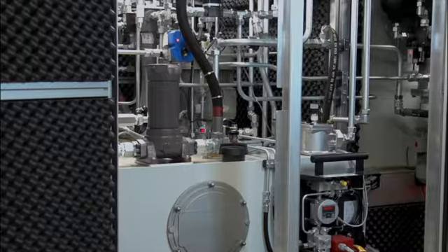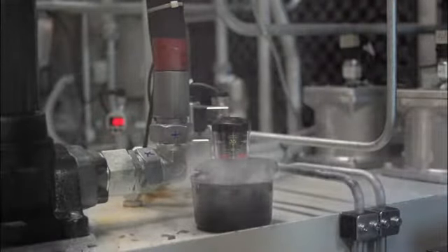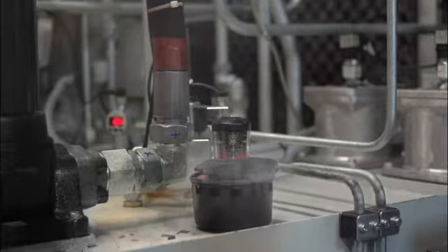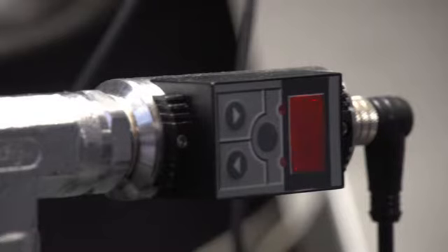The consequences of electrostatic discharge can reach extreme proportions. Uncontrolled discharge in the hydraulic tank can result in dangerous explosions depending on the oil-air mixture. The discharge also causes electromagnetic waves to be emitted. If these waves come into contact with electronic components such as temperature sensors, the latter will be damaged or destroyed.